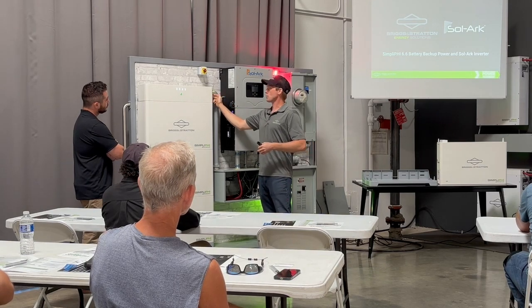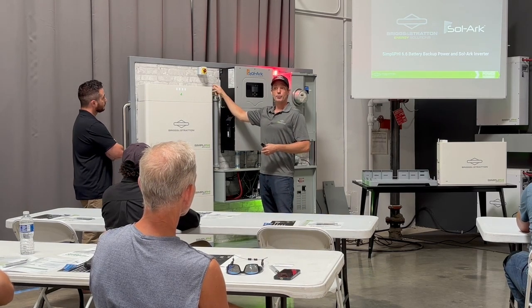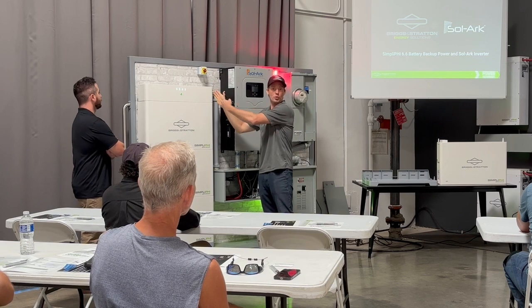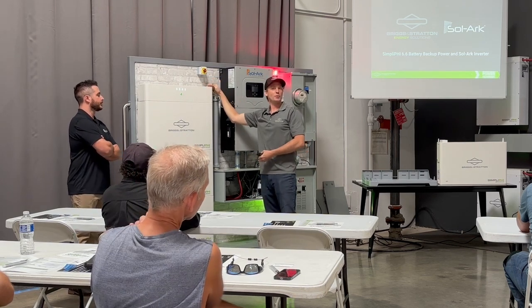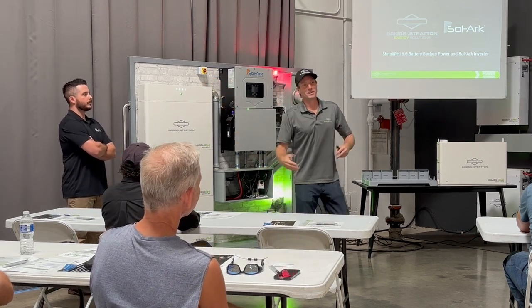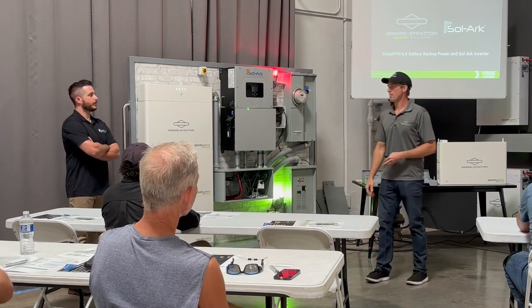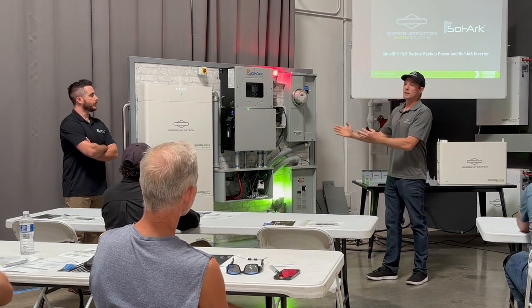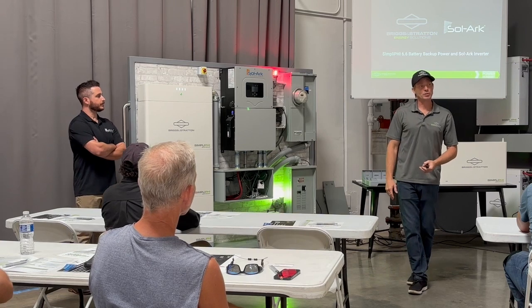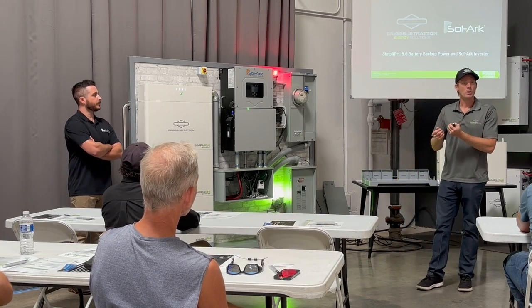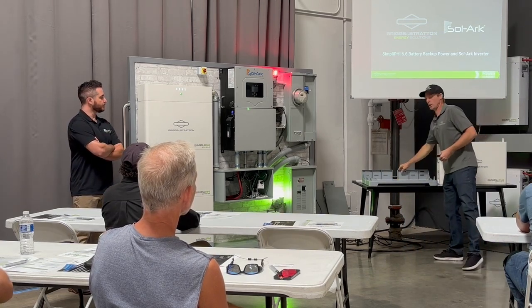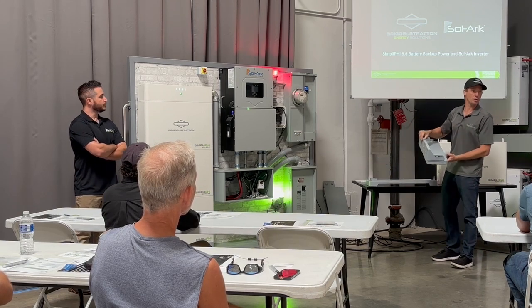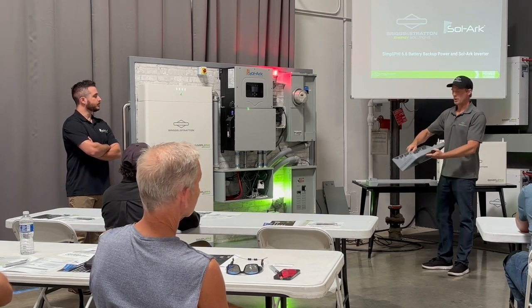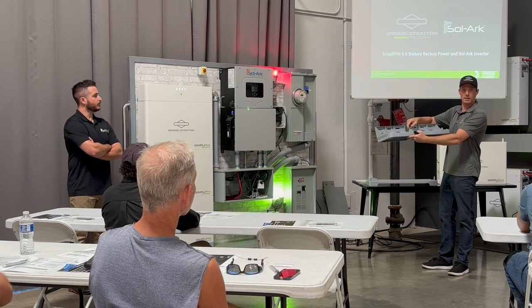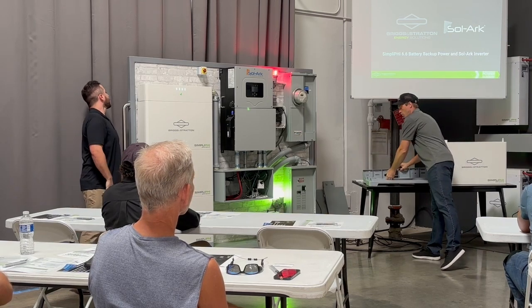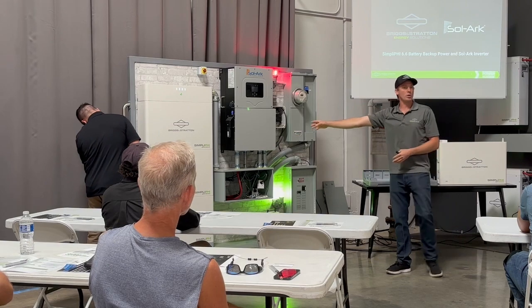So the actual seal for the battery for your conduit coming in is on, there's two vertical plates, and it's on the inner one. You don't have to install the outer one. But if you do, it is a little bit more punchy. But otherwise, it's fairly easy to install, and most people who install outside install it up in the air. So on the wall, because you don't always have a level surface to go to that's 90 degrees to your wall. So this is what the wall mount bracket looks like, and I'll share with you what the whole thing looks like. But let me talk through the training wall to get us oriented.